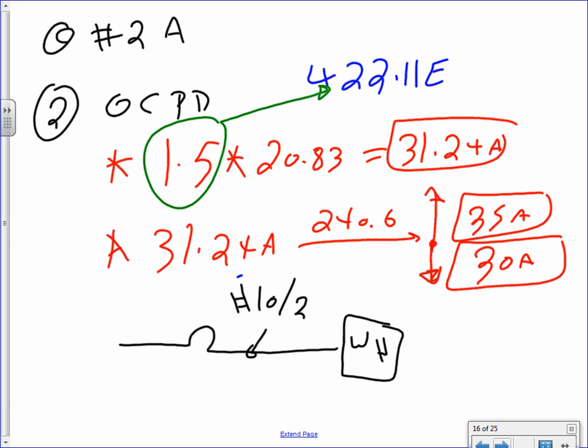Okay, so when I size my overcurrent protection device, Derek, the code allows me to go up to 35 if I want, or down. But I want to remind you the size of the conductor that I already sized was number 10. Can I go up to 35 on number 10? I can't go 35 amps on number 10, because number 10, guys, is limited to 30 amps. You can see there's a decision to make. So if I go up to 35, I have to go up on my conductor. So that's why I would go to 30 amps here. Here's my 30 amp circuit breaker, because my conductor is number 10.